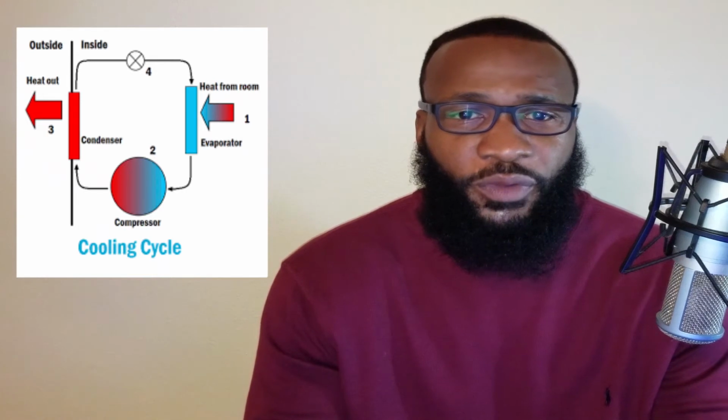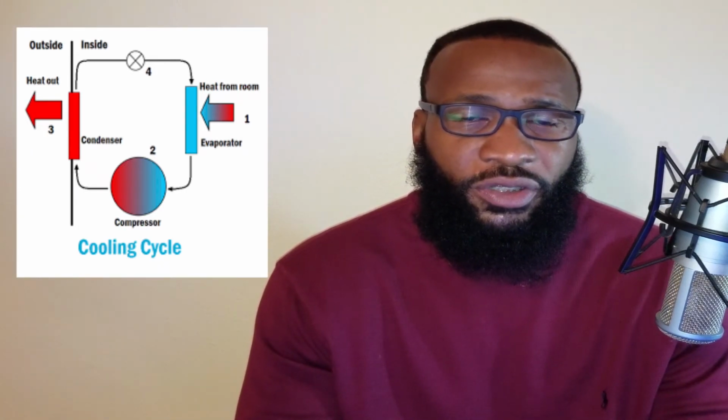And when you're dealing with the regular AC, you're going to have the condenser outside. It's going to be creating a lot of heat with the electricity of the compressor running. The job of a compressor is to pump refrigerant at a vapor state through the system. You can look at the compressor like a heart, and your heart in your chest pumps liquid. Well, a compressor pumps vapor. As it's pumping and pushing, it creates heat, and that's the hottest level of refrigerant at that particular part of the system.